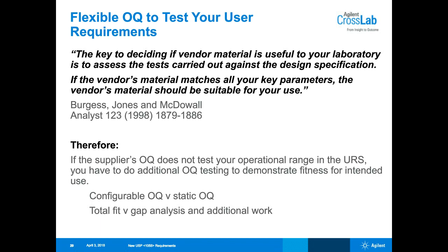And what that means is the operational range in your URS is covered by the OQ, and you show the instrument is fit for use. The problem is that if you just have a static OQ and you are working outside of that operational range, you have a potential problem because that use outside the operational range is not qualified. So you have a choice.